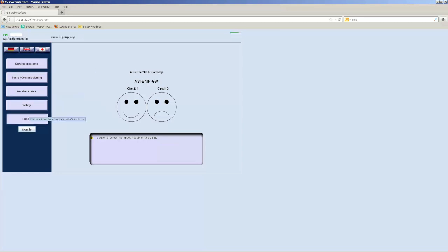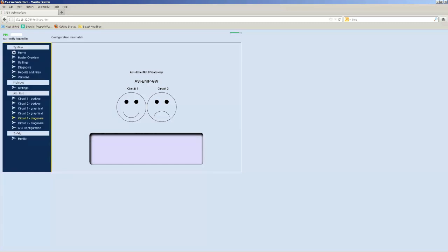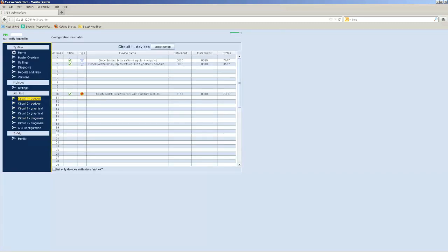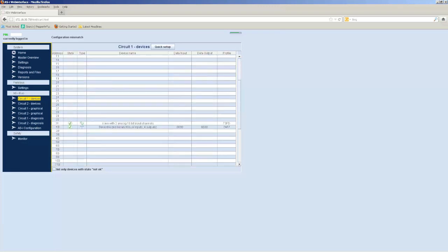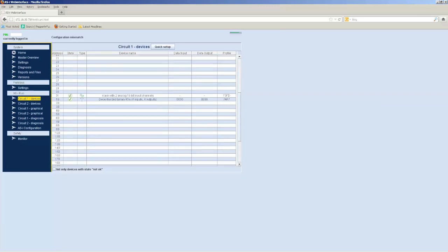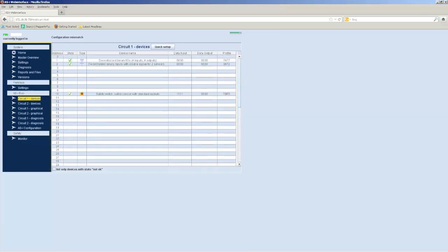First thing I'd like to do is go to Expert Mode, and I choose Circuit 1 Devices. This will allow me to double-check any of the devices on the network. You can see I've got 1A, 2A, and address 10 is my e-stop. Address 31 is my analog node, and then address 1B I have on as well. Okay, so my five devices.